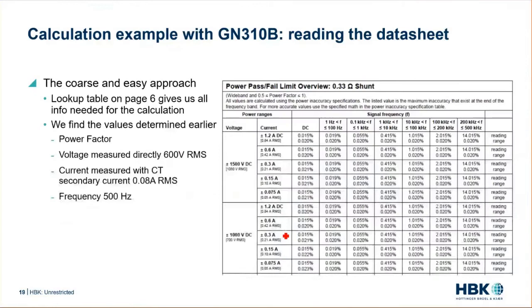Let's get to reading the GN310B data sheet. First, the coarse and easy approach: looking at the table on page 6, which gives us a lookup table with all the info we need for our calculation. We need to find the values we determined earlier. The power factor is 0.8, which fits the range between 0.5 and 1. The voltage we are measuring directly at the input is 600 volts RMS, so we are in that input range.